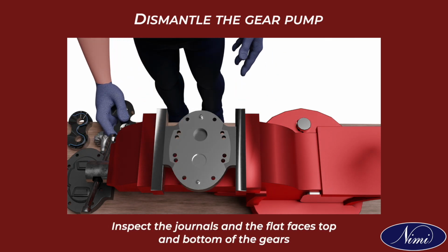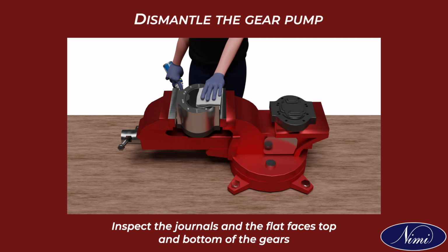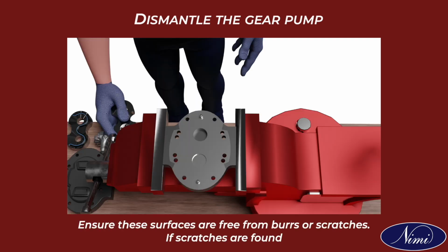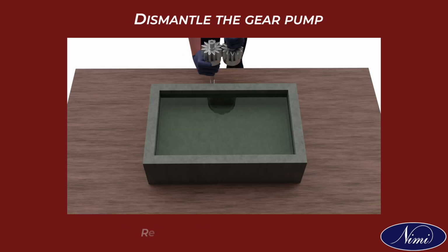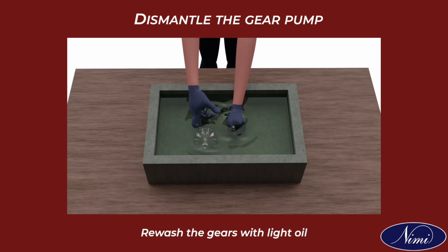Inspect the journals and the flat faces, top and bottom, of the gears. Ensure these surfaces are free from burrs or scratches. If scratches are found, clean them with very fine emery cloth. Rewash the gears with light oil.